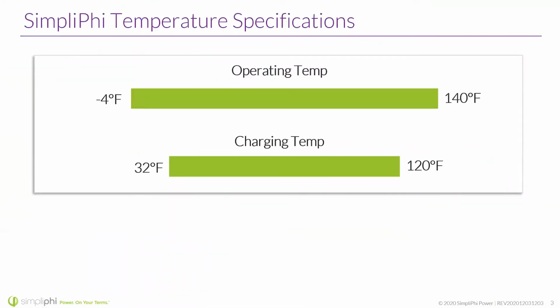So as far as our specifications go on the batteries, operating temp, -4 Fahrenheit to 140 degrees Fahrenheit, and charging temperature of 32 degrees Fahrenheit to 120 degrees Fahrenheit. So basically, something to consider here is operating versus charging.